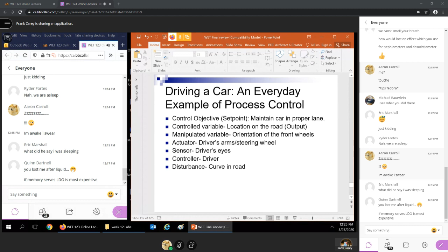You should be able to say what the actuator is - in that case it's the solenoid. What the sensor is - the thermocouple inside the thermowell. What the process variable is - the temperature of the pipe, since the pipe is being heated up. So anybody should be able to do that.